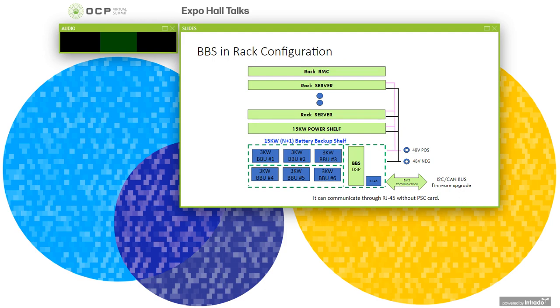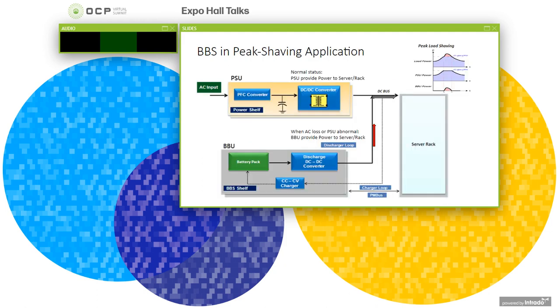In previous designs, if charger-discharger are integrated within the PSU, then the BBU module will have a lot of power and signal interconnection with the PSU, making it less modular. Now, with our proposed ORV3 design, this slide shows how BBS is connected within a rack, and it only connects to the 48-volt bus. The communication port is for external access to its control and monitoring.